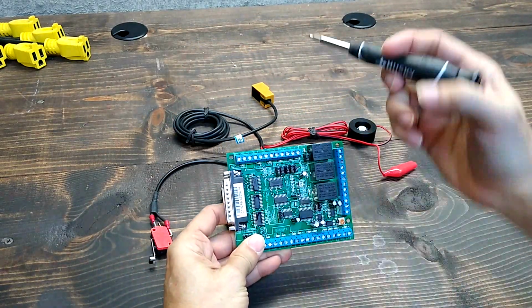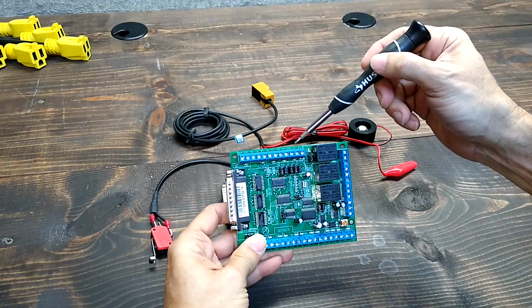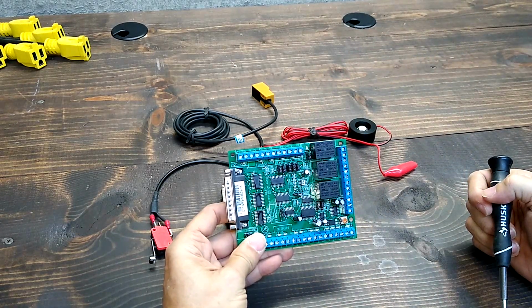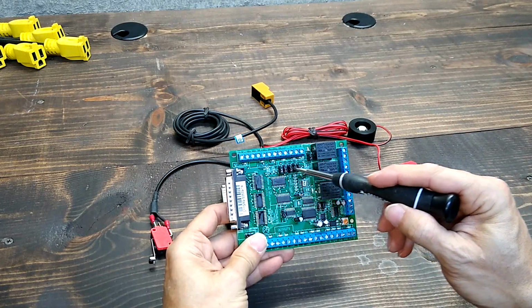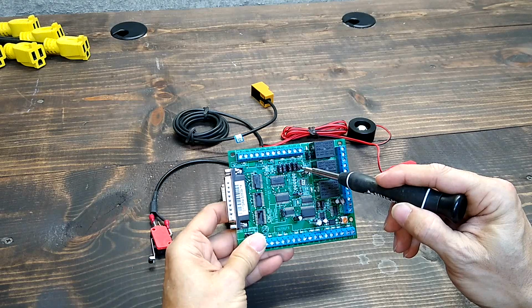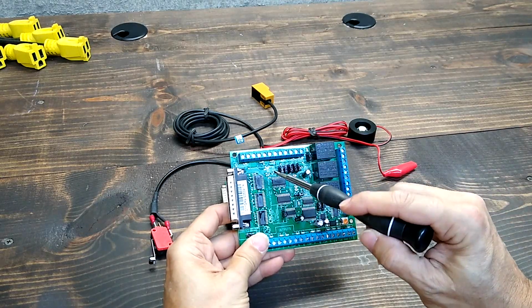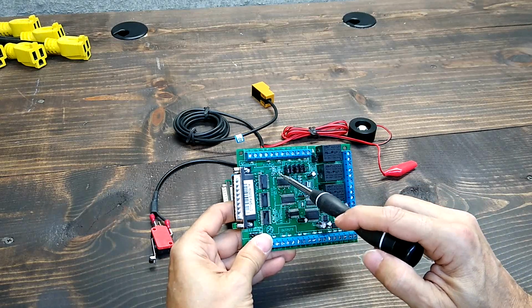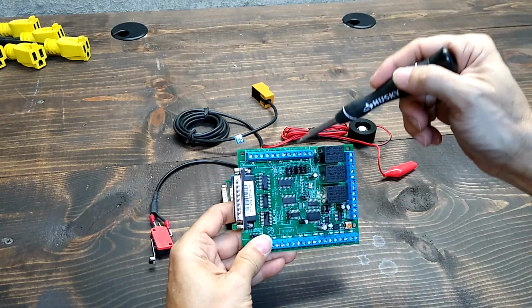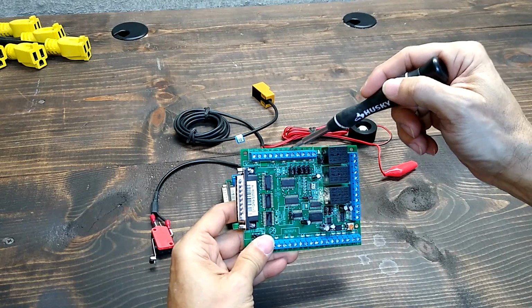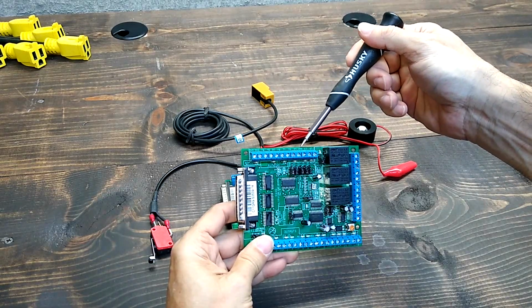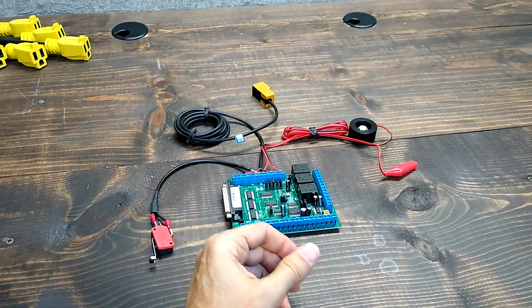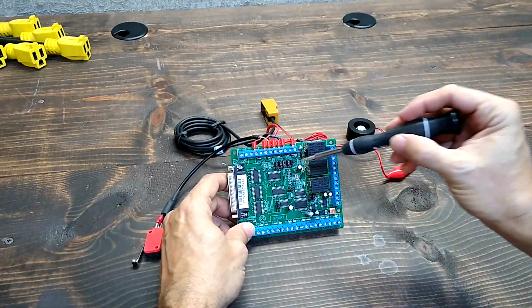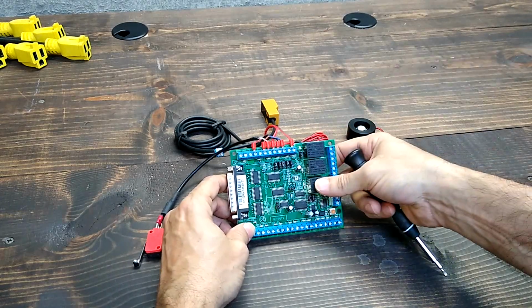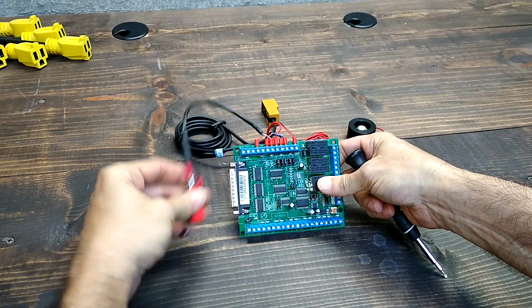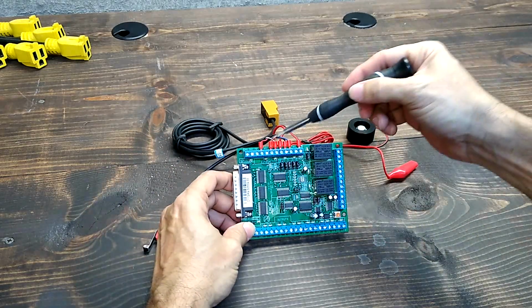For inputs, we have pin 10, 11, 12, 13, and 15. Now, if the inputs are 5 volts, jumpers should be set to pull down. If inputs are ground, then jumpers should be set to pull up. We have input terminals, 5 volts terminals, and ground terminals. In this case, jumpers will be set to pull down, we have a mechanical limit switch connected from 5 volts to input 11.